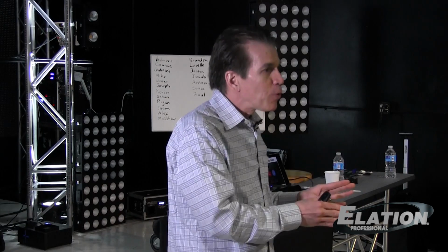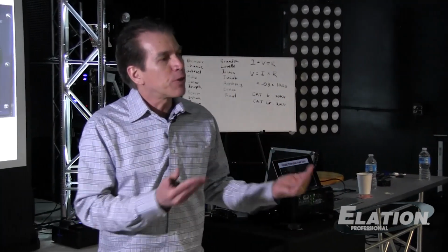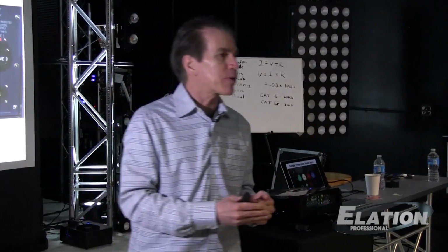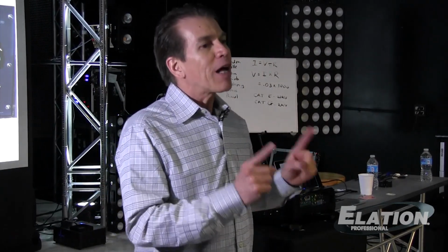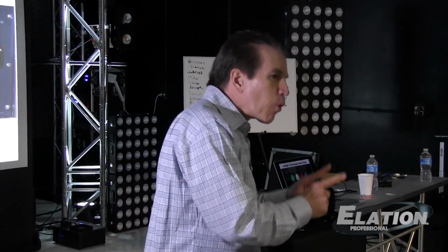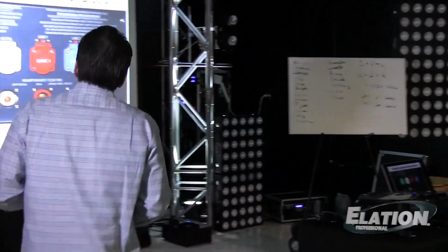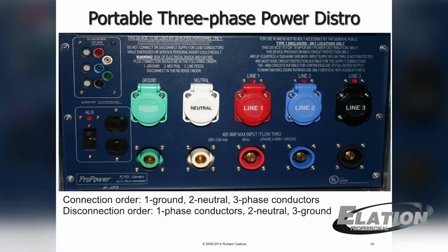And there's different rules, different codes that apply to portable than apply to temporary. Some inspectors will confuse the two, in which case it can cause a lot of trouble. So when you're talking to an electrical inspector, the terminology you want to use is portable, not temporary.